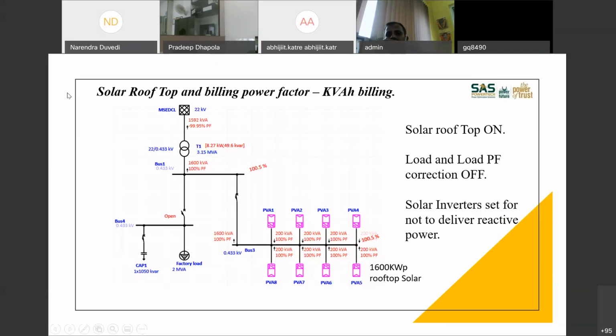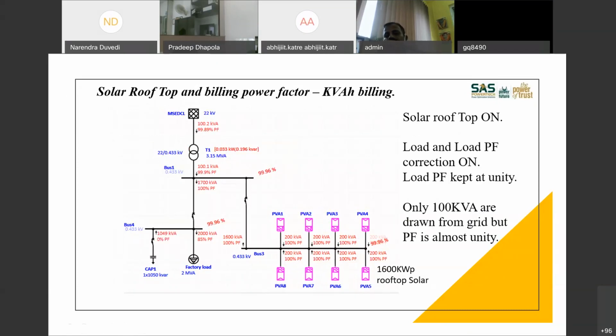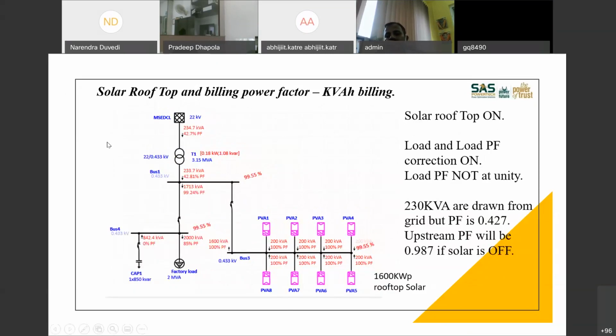What I tried to explain was, your problem will get more addressed if you see this. See here, what has happened is I am generating 1600 kWp. I am using the same 2 MVA load as I was using earlier. Now my 2 MVA load here is not fully compensated by my plant capacitors, right? So the entire generation I can use here as far as the active power is concerned, but the balance reactive power I have to take from the grid. If I take that balance reactive power from the grid with very few kilowatts, then my power factor becomes very low. So what I was trying to explain was your reactive power requirement comes from the load.